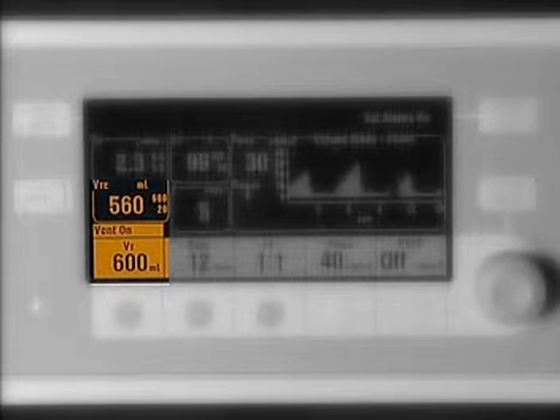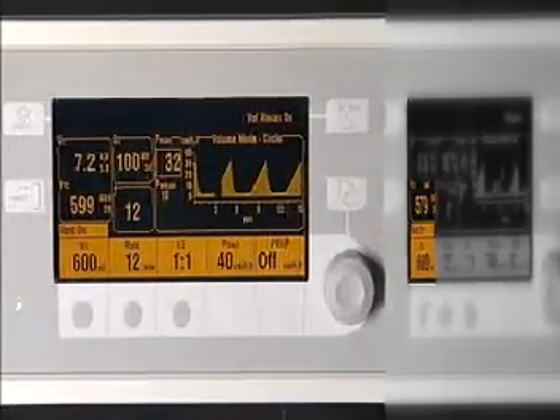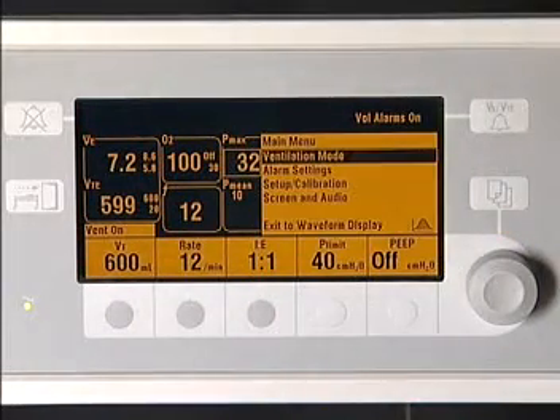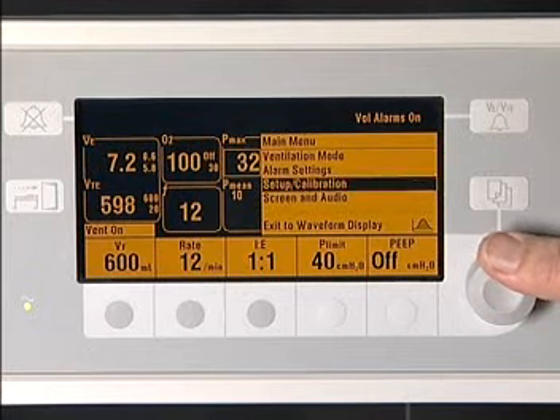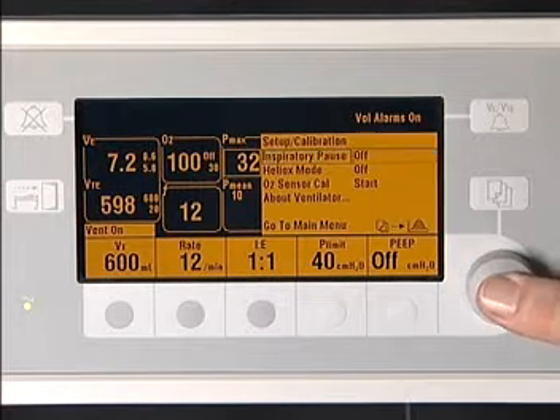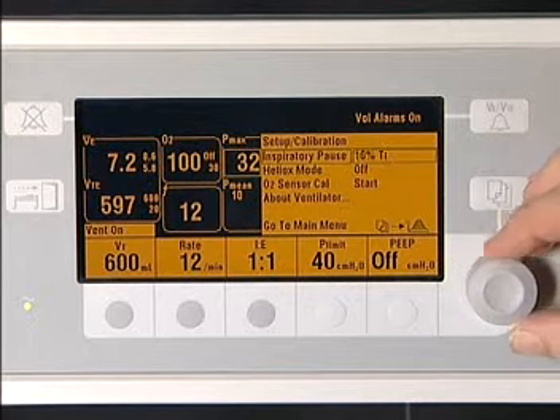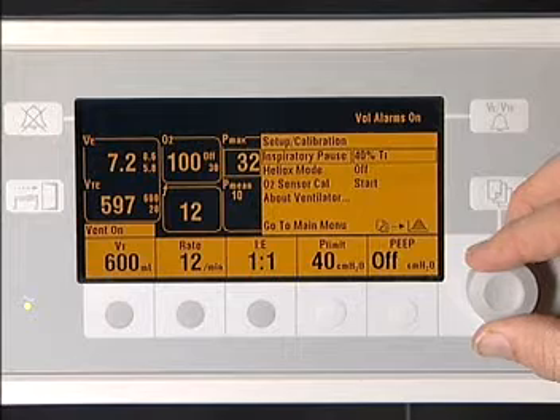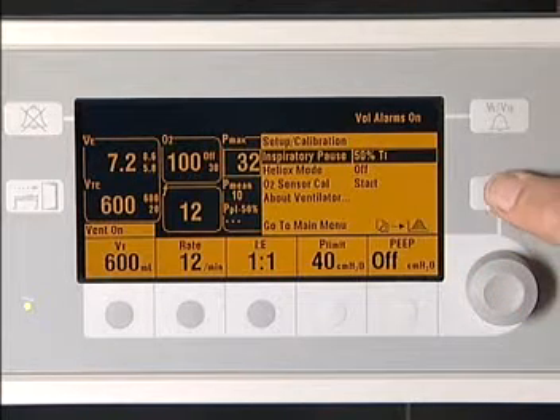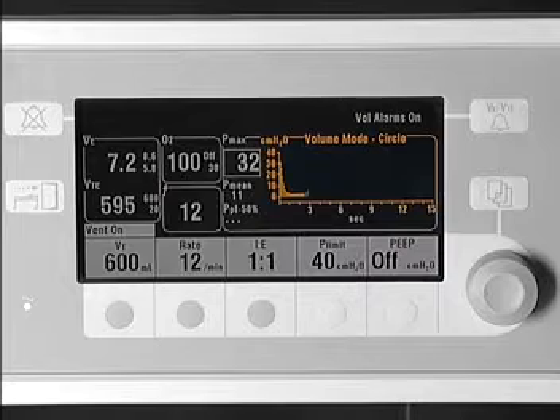Volume control ventilation utilizes the tidal volume compensation mentioned previously. If there is a change in parameters during the case, the ventilator will move to the new settings over a 5 or 6 breath interval to be certain values are not overcorrected. Within the volume mode, the user has the capability to modify the pressure waveform via the ventilator setup menu using the inspiratory pause feature. A pause of 5% to 60% is available. The processor in the ventilator will modify its flow settings to deliver desired tidal volume in the remaining inspiratory time.